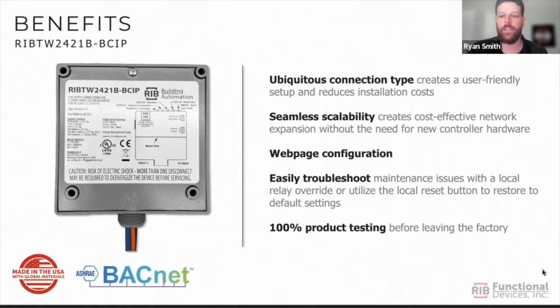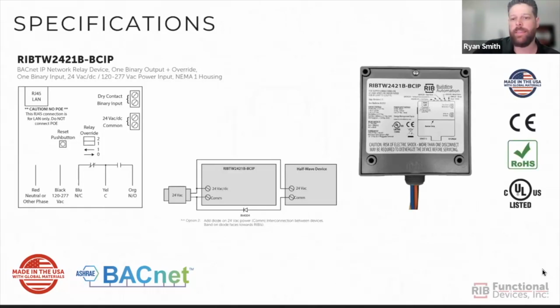And once the relay is configured, you can troubleshoot equipment issues with a local relay override. And then the relay is easily reset to default settings by hitting an onboard reset button. And once again, this device is 100% tested before it reaches your hands, so you know the product will work once you add it to your network. So here's a look at the internals of the relay. The Ethernet connection is actually located on the top left side of the enclosure, not in view in that picture, but inside the relay, you'll see a binary input connection there at the top right corner. This is for adding a current switch or a flow switch or any other binary input you need to add to your sequence.